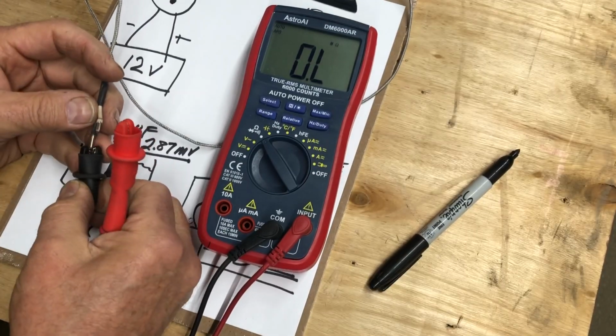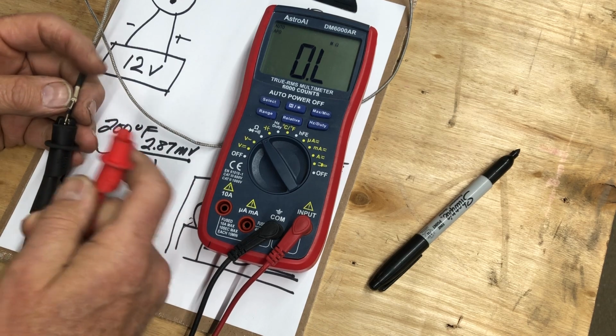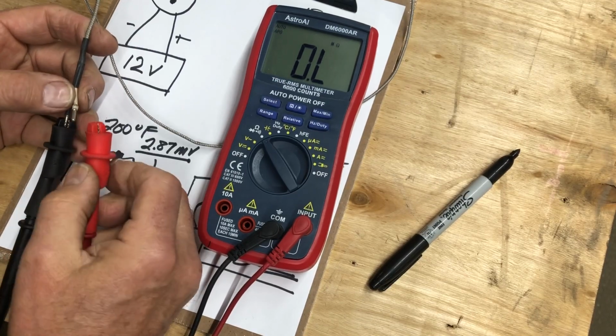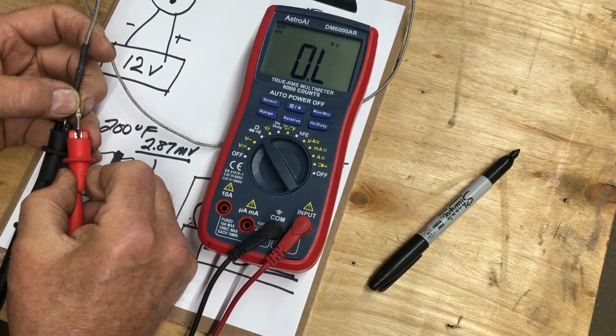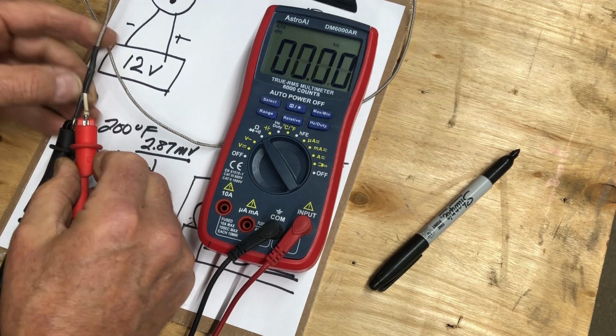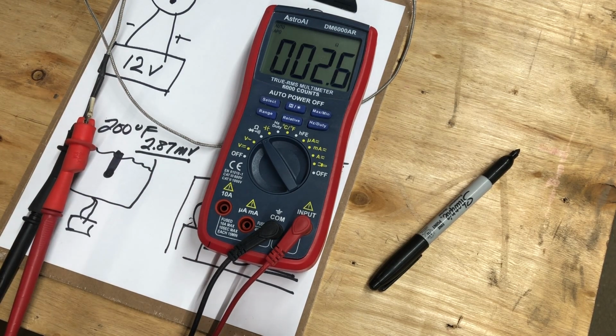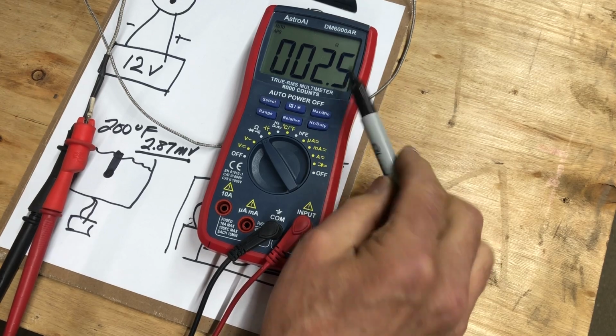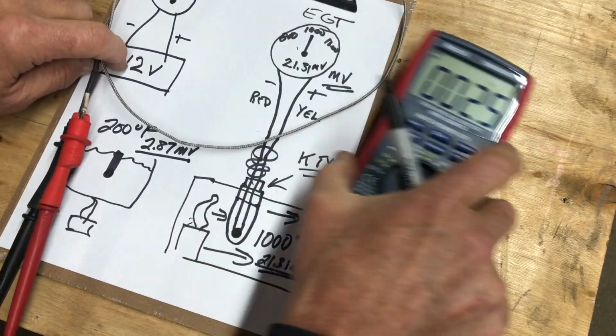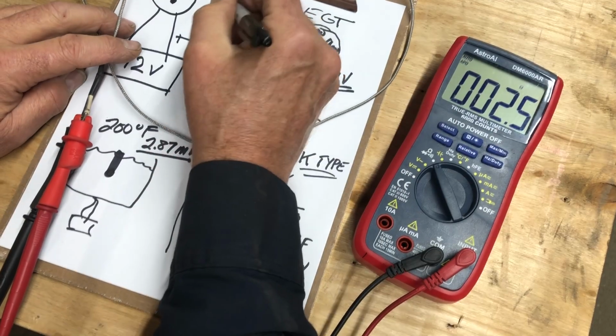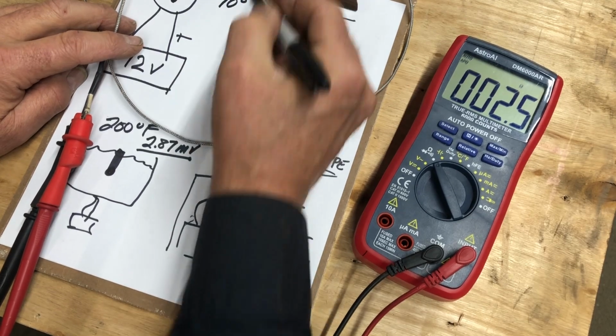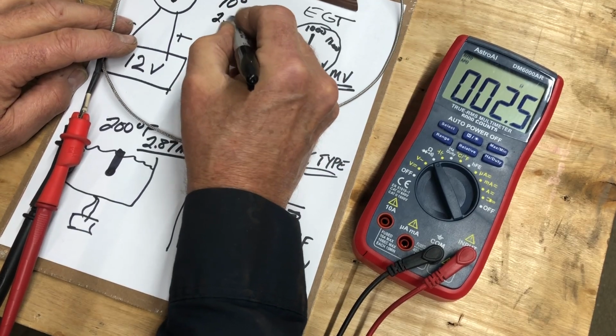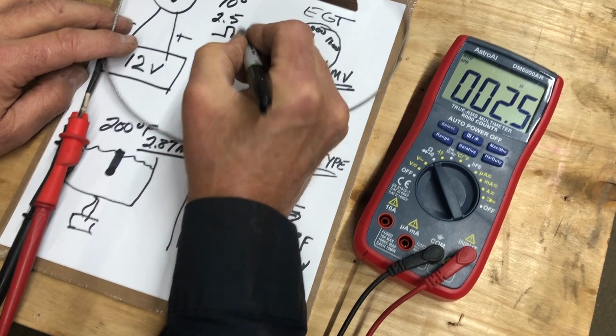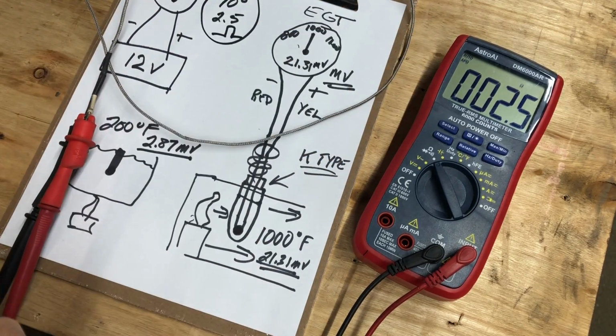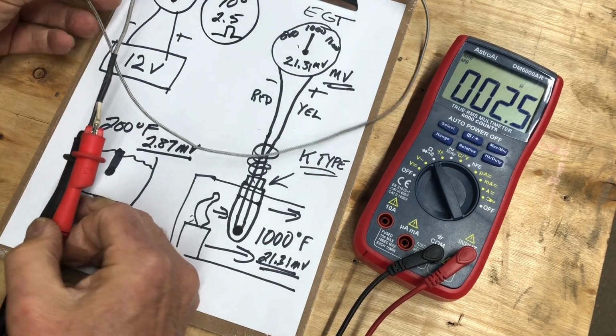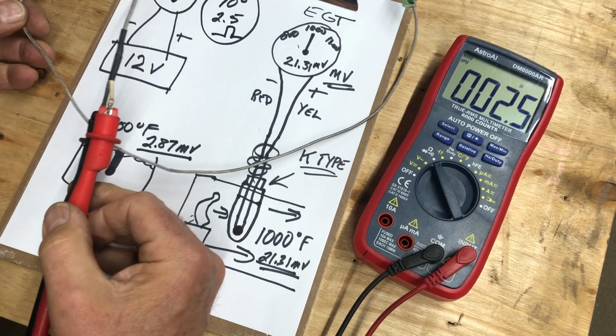Now, when checking the ohms on these, say your EGT just stopped working, one of them dropped out and doesn't do anything. Right on the airplane at room temperature, so 68 to 70 degrees, we should get 2.5 ohms, there's another spec right there. So at 70 degrees we'll get 2.5 ohms resistance. At this point, I can say, well okay, it has the capability of that.